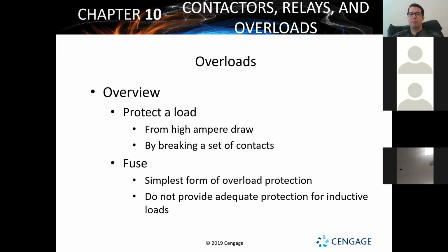Now the reason we have a fuse used as a safety is as our last resort. That's one of the ones that really, if there's something majorly wrong with the system, something pulling way too much power where we're going to damage the electrical and the rest of the house, or damage the breaker panel, or just run up the electric bill forever because the system was stuck on or something like that - that's when you can pop a fuse. And that's when it's going to say, okay, shut it down because obviously it's not working properly, so let's get someone out here to look at this thing.